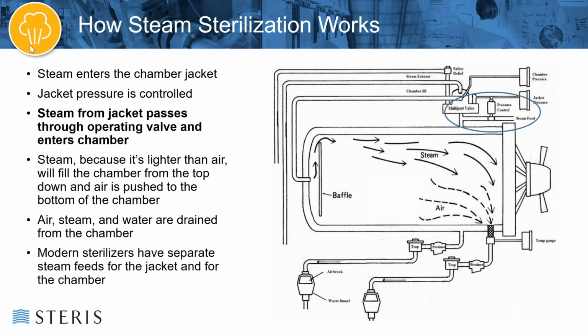This representation is an older model of sterilizer. Some of the newer models of sterilizers will actually have a separate steam feed for the jacket and the chamber. So in this instance, there's the steam feed that would come here and feed the jacket. This steam feed would bifurcate at some point and then would come into this line to fill the chamber, and they wouldn't actually be connected in any way. So most of the modern sterilizers are typically set up that way, with separate steam feeds for the jacket and the chamber.